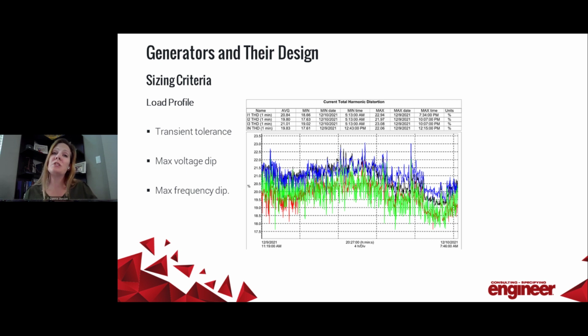One way to improve motor starting is by minimizing the generator reactance or upsizing the alternator. Similarly, in order to minimize harmonics, you could add active or passive filtering to your loads, and you could also consider upsizing the alternator to minimize the source impedance. There are also certain sensitive loads in many systems. I know a lot of people said they're working on hospitals and data centers, so you're certainly dealing with sensitive loads there. Those cannot tolerate large voltage drops or frequency dips. For instance, you could have a fire pump connected, and the codes dictate that no more than a 15% voltage drop is allowed when the systems come online. So again, the size of the alternator may need to increase to handle the load.